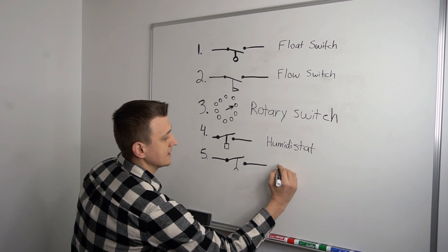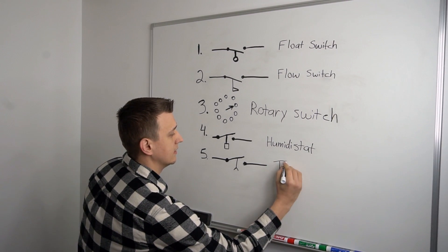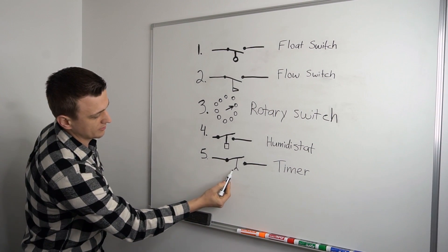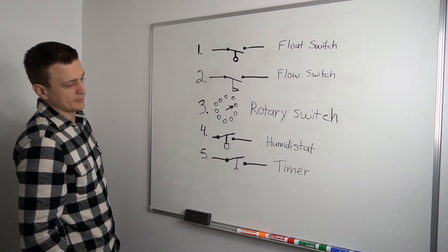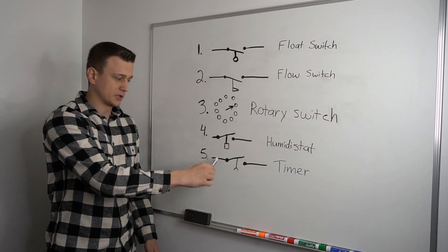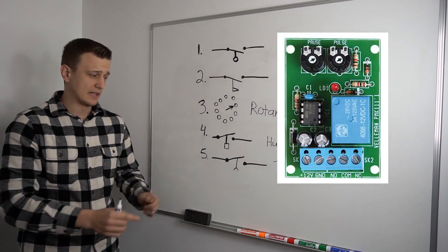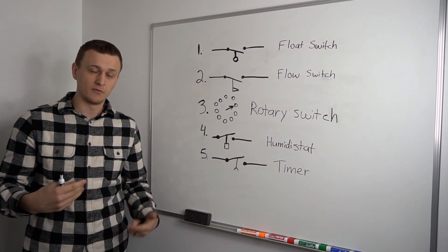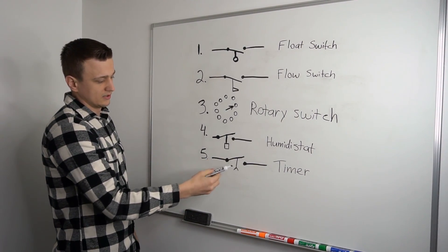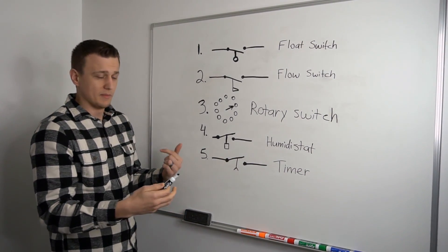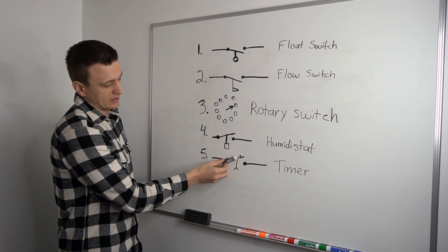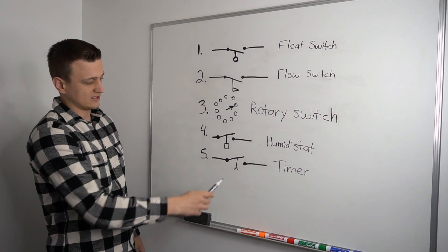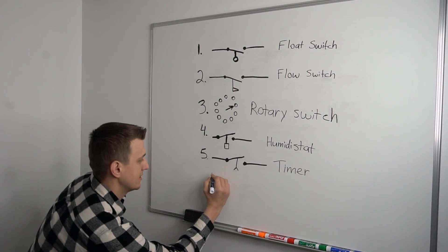This one right here is a timer. A timer switch. So whenever you see a line with like a triangle without the bottom piece there, that stands for a timer switch. And most of the time, timer switches like this can be found in time delay boards. A lot of times you'll find them in the control board in the condenser unit outside. It delays it by about five minutes before it starts. And once again, this is a timer. So as the minutes go by, this little switch starts to go down, down, down until it clicks and lets the power through and the unit turns on.